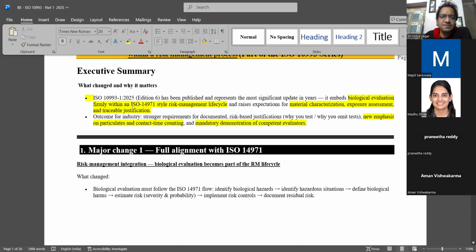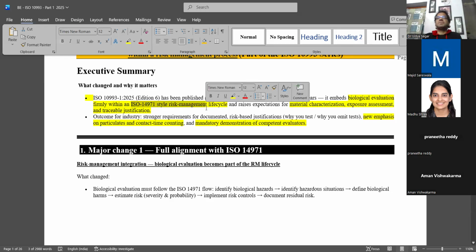So what it says is the biological evaluation is firmly integrated with risk management. I know it was integrated earlier also, but this time the risk from biological evaluation has to be a separate document. Like how we write the risk management report, where we identify the hazard, situation, harm, risk analysis, evaluation and risk controls in a tabular form, even for biocompatibility you need to provide it separately in your biological evaluation report. You need to provide separately what tests you are doing, what the basic biological endpoints are, and what risks they carry.